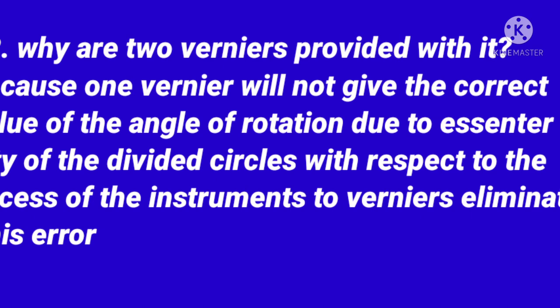Why are two verniers provided with a spectrometer? Because one vernier will not give the correct value of the angle of rotation due to eccentricity of the divided circles with respect to the axis of the instrument; two verniers eliminate these errors.